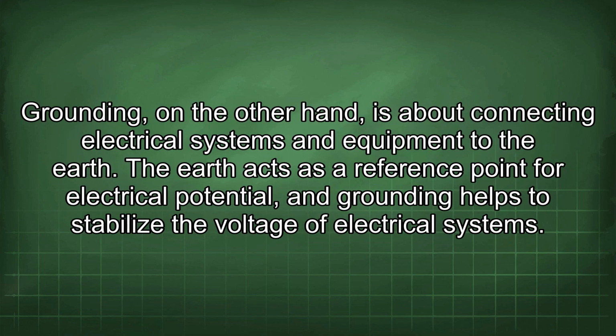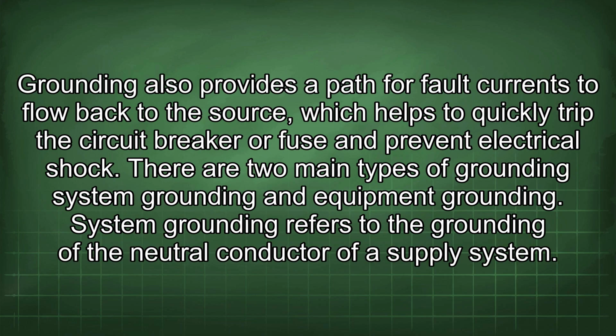Grounding, on the other hand, is about connecting electrical systems and equipment to the earth. The earth acts as a reference point for electrical potential, and grounding helps to stabilize the voltage of electrical systems. Grounding also provides a path for fault currents to flow back to the source, which helps to quickly trip the circuit breaker or fuse and prevent electrical shock. There are two main types of grounding: system grounding and equipment grounding.